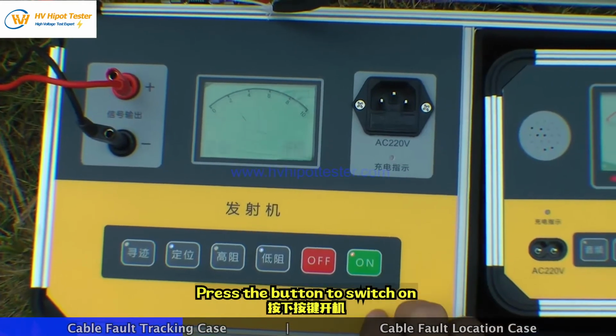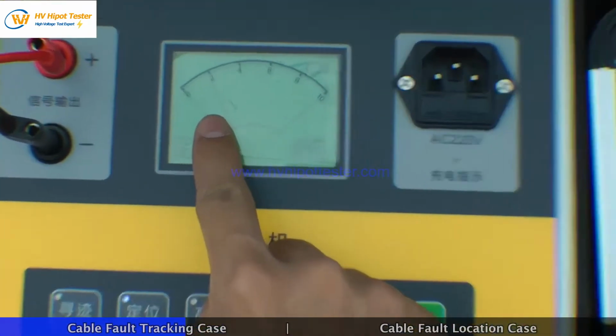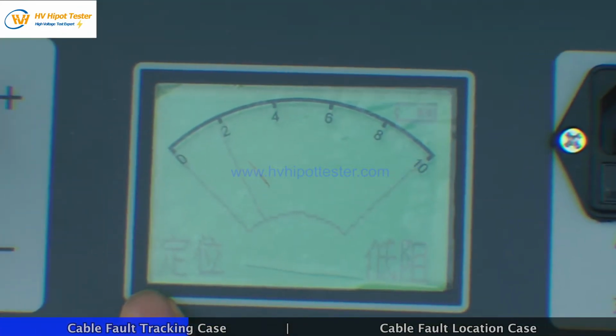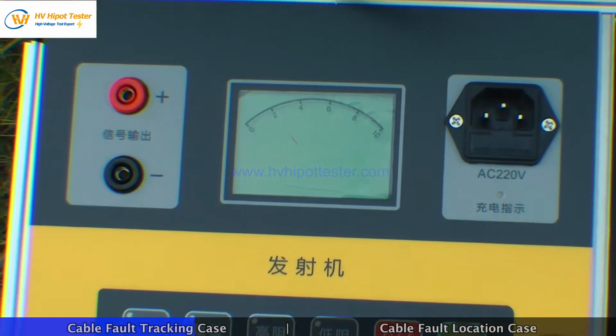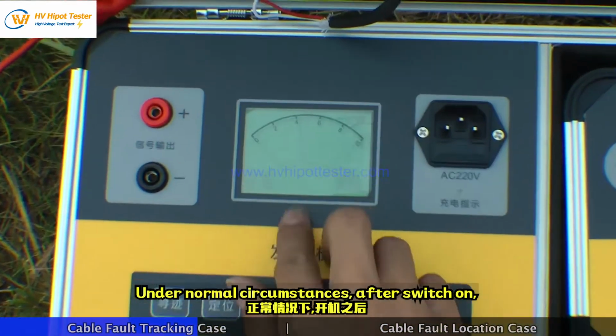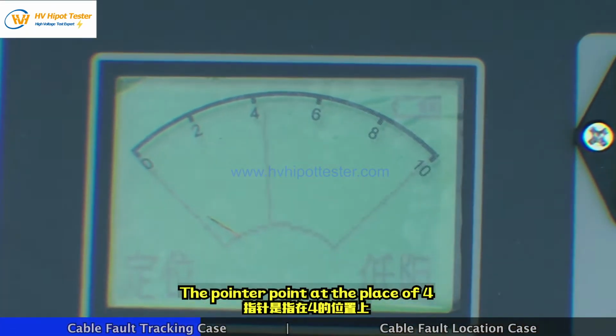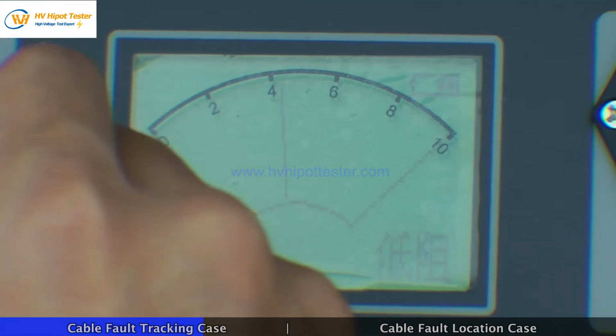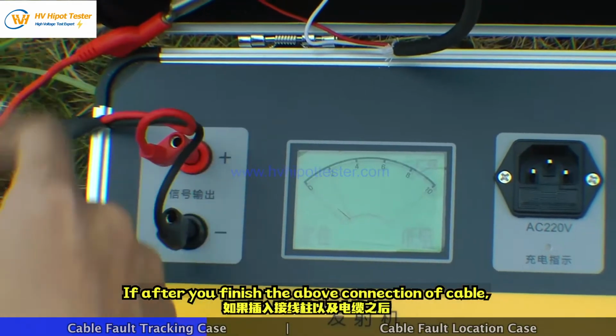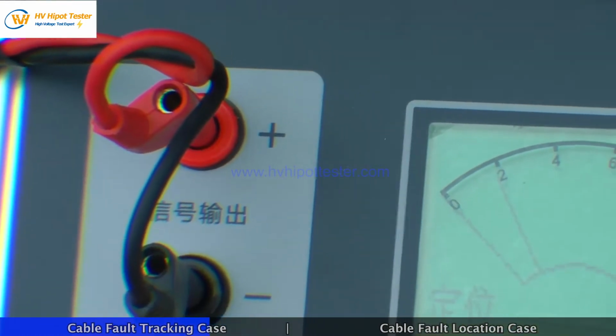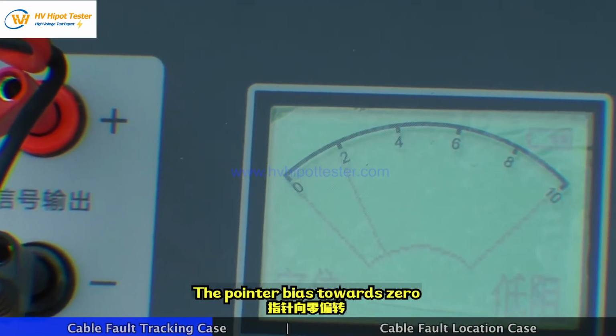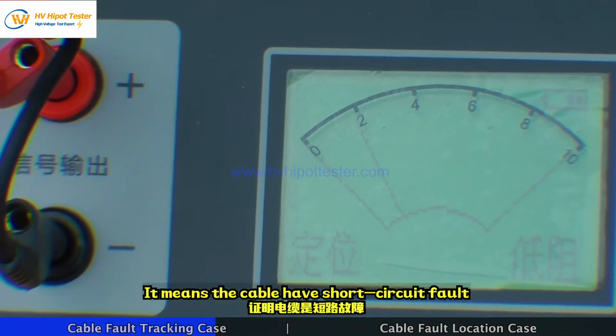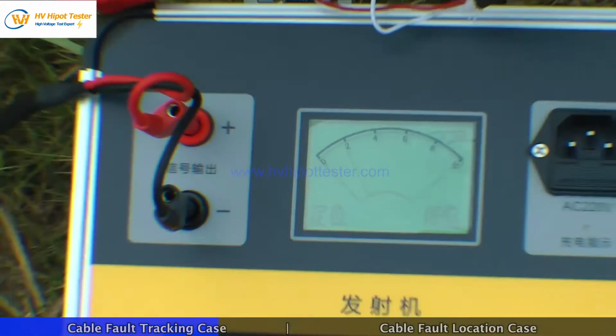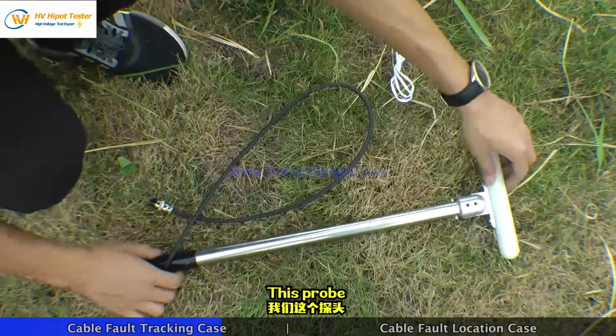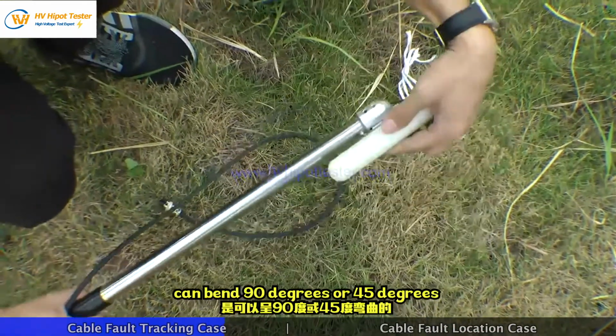Press the button to switch on. Pointer bias to 0. Under normal circumstances, after switch on, the pointer points at the place of 4. If after you finish the above connection of cable, the pointer bias towards 0, it means the cable has a short circuit fault. This probe can bend 90 degrees or 45 degrees.